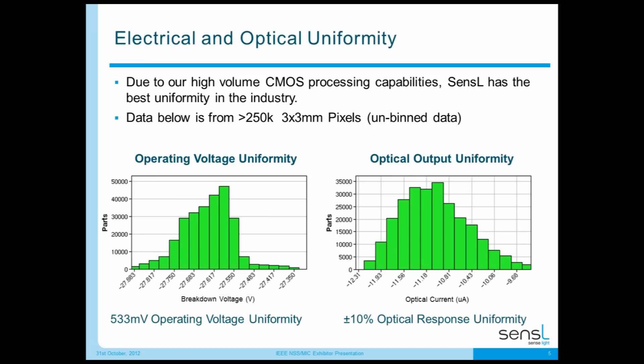Regarding electrical and optical uniformity — this is very important when incorporating many silicon photomultipliers into a product for volume production. Due to our high-volume CMOS processing, we have the best uniformity in the industry. We're showing data taken from over 250,000 3×3mm pixels — un-binned data coming off wafers as produced and tested electrically and optically. On the left-hand side we show breakdown voltage variation across those 250,000 parts — about half a volt of operating voltage uniformity across our entire product range.